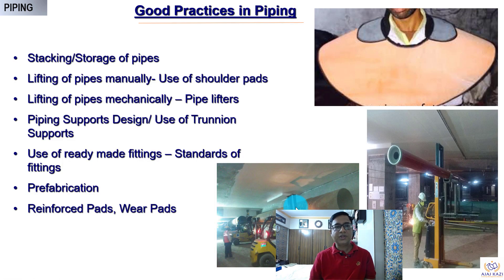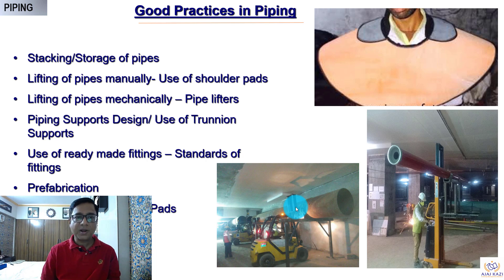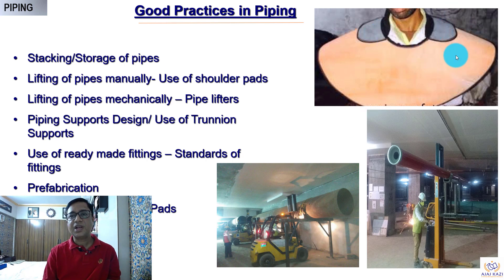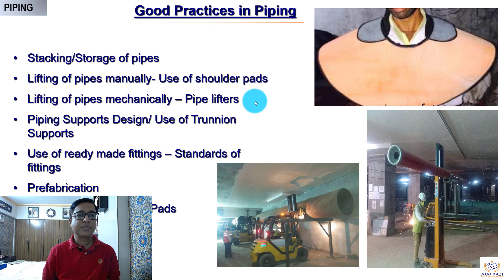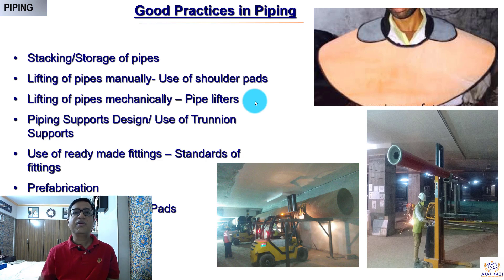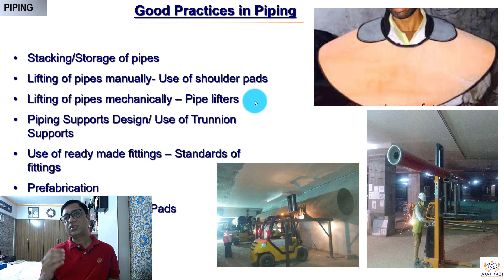Some good practices to look at: how do we store the pipes — this has to be done properly. How do we lift the pipes? Pipes below 100 mm have to be lifted manually, and when lifting manually, a shoulder pad is used so the pipe does not rest directly on the person's shoulder. Mechanical lifters can also be used as shown in the photographs. We need to have the right fittings available. For tap-offs specifically, it is better to do the work off-site — take measurements and fabricate off-site — because doing everything on site impacts quality, safety, and productivity.